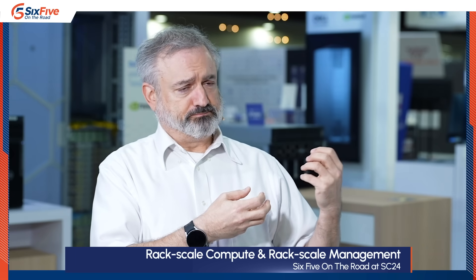That works when you're talking about 10 to 15 kilowatts per rack. But what are we talking about today? We've got racks that range anywhere from 50 to 60 kilowatts all the way up to 130 kilowatts. Once you get above that 40 to 50 kilowatt limit, you have to do liquid cooling. Generally you'll also need rear door heat exchangers so that you can get all of that heat rejected to liquid and sent out of the data center to be cooled.